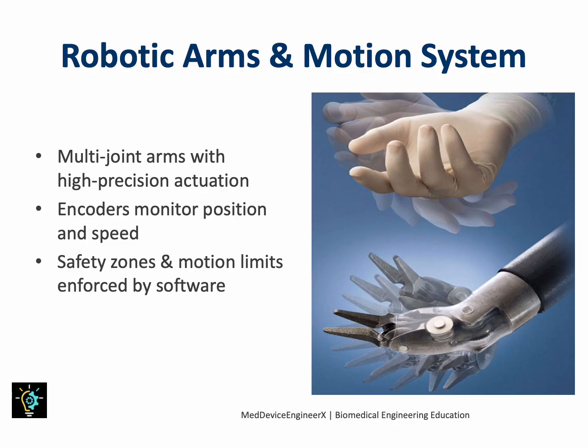Encoders are located inside each joint, continuously measuring the angular position, velocity, and direction, allowing the control software to monitor and adapt motion in real time. This creates a closed-loop system where the robot constantly corrects itself to stay aligned with the surgeon's input. Safety is deeply embedded. Virtual boundaries, collision avoidance routines, and force-limiting algorithms prevent the arm from moving in ways that might harm the patient. Biomedical engineers often service these arms by checking mechanical wear, verifying the encoder health, and running diagnostic movement tests. Understanding this hardware-software relationship is key to maintaining reliability.